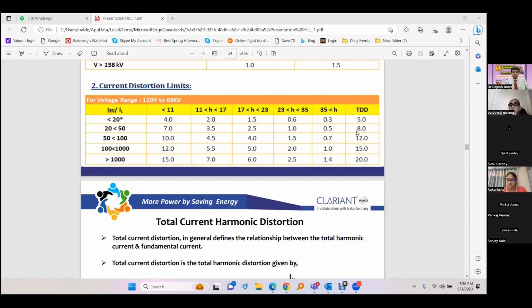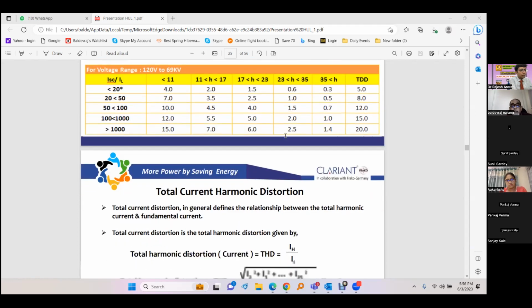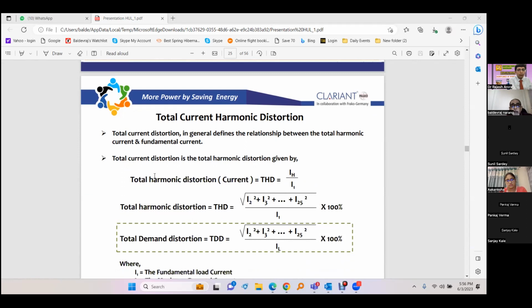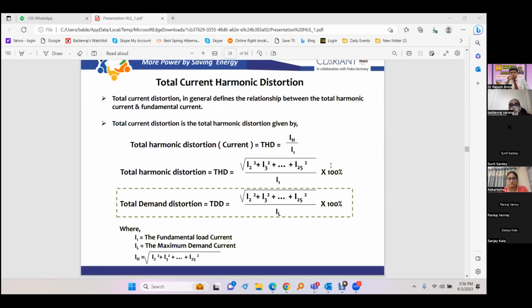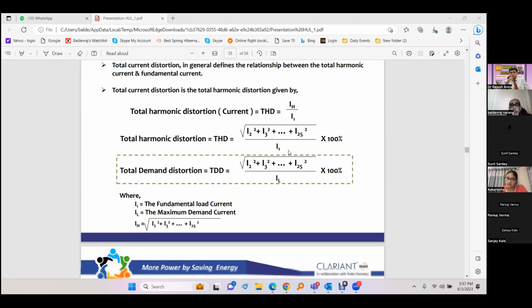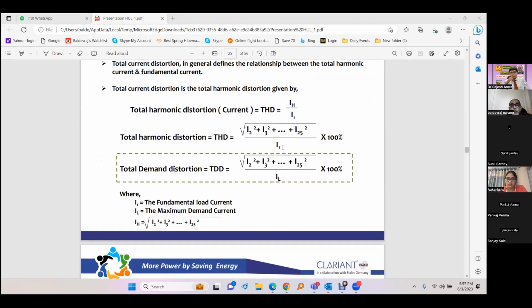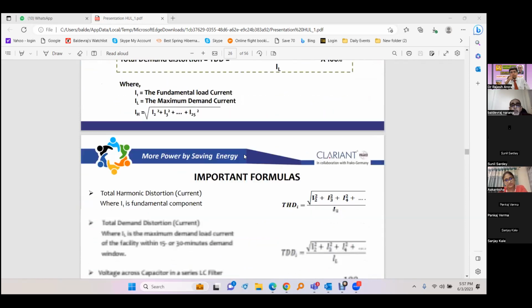TDD is related to the maximum load current and THD is related to the fundamental current. And that doesn't indicate any severity at all. So whatever THD we measure from the analyzer, we convert it to TDD. Now the meters themselves convert directly to TDD. And if the TDD is within 8%, mostly it is considered safe. So these are just formulae. Total harmonic distortion we calculate like this, and demand distortion is with respect to the load current, and THD is with respect to the fundamental current. So these are just simple formulae.